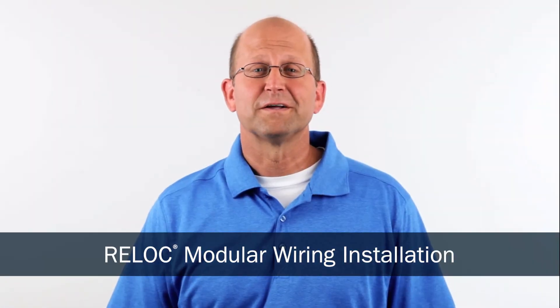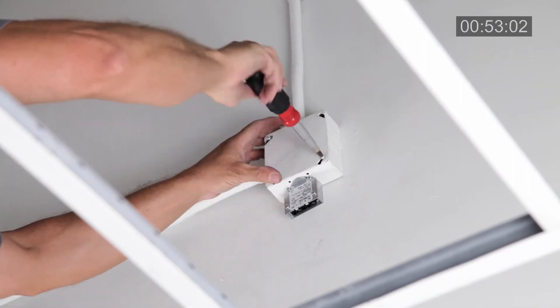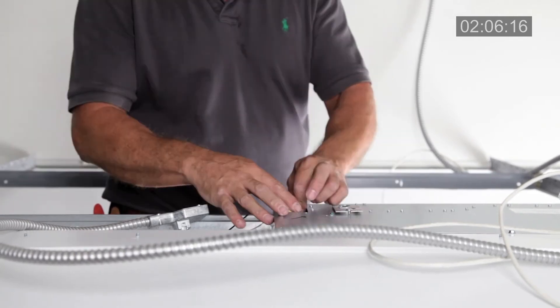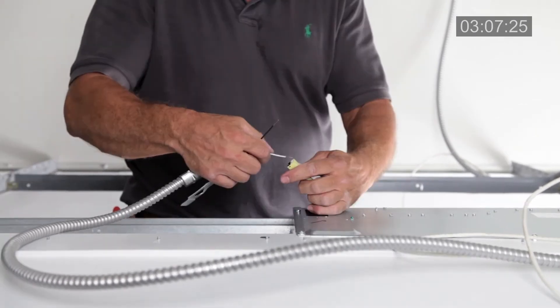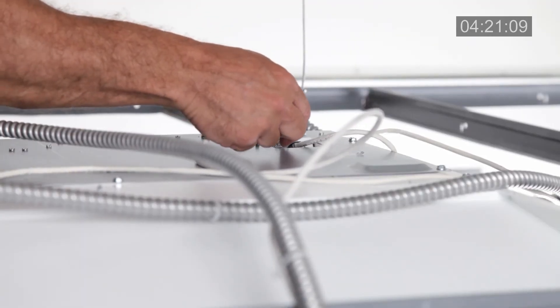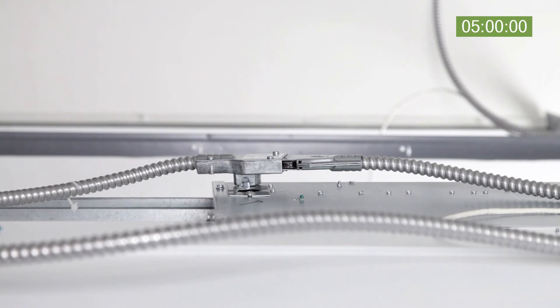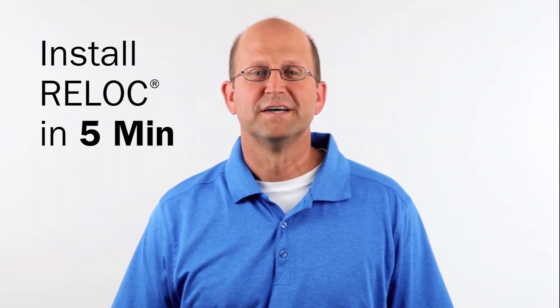Now let's look at installing the same fixtures with RELOC. Simply install the RELOC starter component into the Home Run J-Box and the rough end is complete. Using the one-pass fixture cable, poke home the hot and neutral driver leads at the access plate knockout and snap the one-pass cable into the knockout. It is UL listed for auto grounding so there is no ground wire required to terminate. Lay your fixture into the ceiling grid and plug the loose end into the starter device at the Home Run location or into the end of the previous fixture and repeat until the run is complete. The typical time to install your fixture using RELOC is five minutes. That's four times faster than MC cable and that puts more money in your pocket.